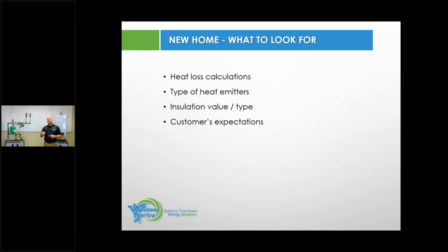Normally with hydro air, we would run a little higher temperatures unless you're really, really focused and driving the temperature down, which is a great thing to do. But the majority of the time, if we're looking at a hydro air type system, we're looking at higher water temperatures in our boiler system, and this is something to keep in mind next week when you're doing your design.